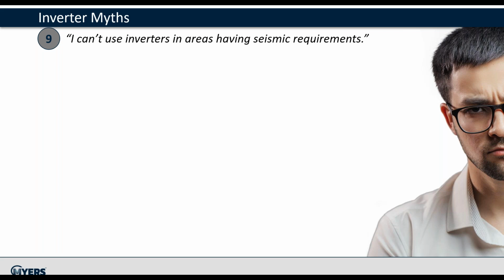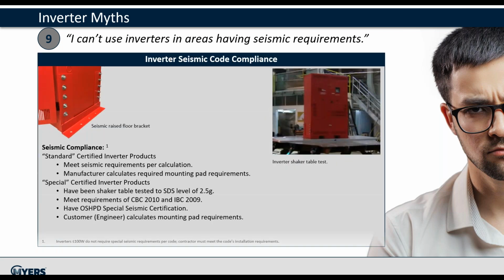The final myth is I can't use an inverter in an area having seismic requirements. There are two versions of seismic ratings available, which are classified as standard seismic and OSHPD seismic. Standard seismic ratings are calculations performed by a certified engineering firm on bracing, mounting pad, and mounting brackets, ensuring that the inverter will not fall over in the event of an earthquake.